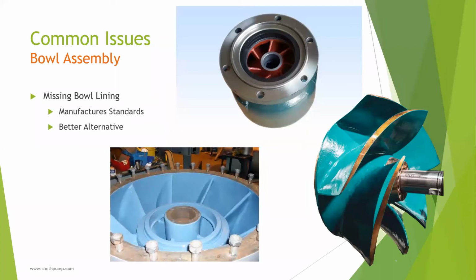Bowl lining is a fairly standard practice in the vertical turbine world. So lining a bowl serves two purposes. It smooths the casting walls to increase efficiency. It also protects the bowl from erosion and corrosion. Typically small bowls, somewhere around 20 inches or less, have their interior water passages coated with porcelain that's baked on for a hard but smooth finish. It's the same finish you see on a toilet or a porcelain sink.